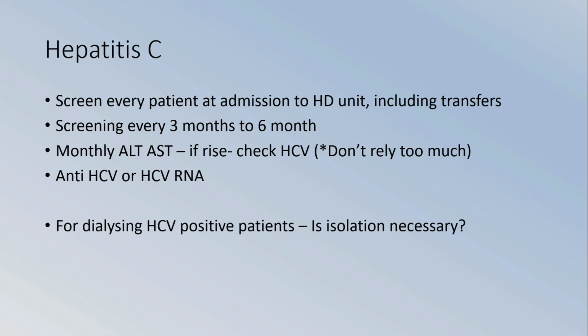At the time of design itself, we designed it such that there will be a separate room for HCV. The staff stays inside, the reprocessing happens there only, and those machines are obviously dedicated. And since then, we have had hardly any HCV transmission.